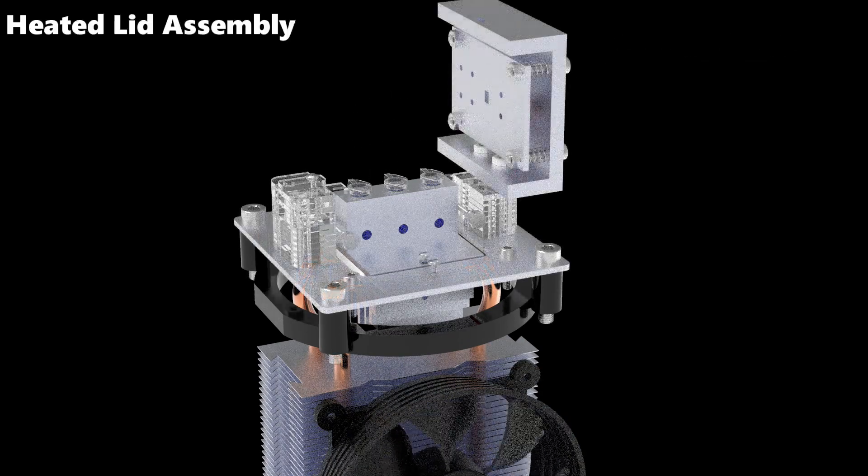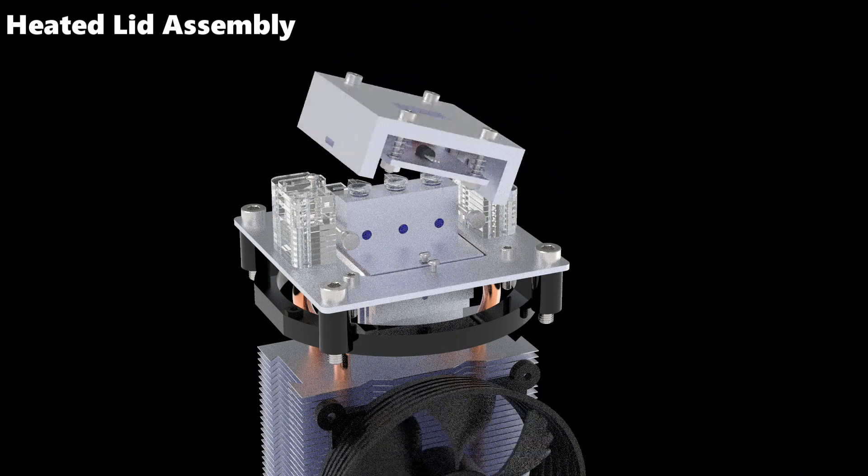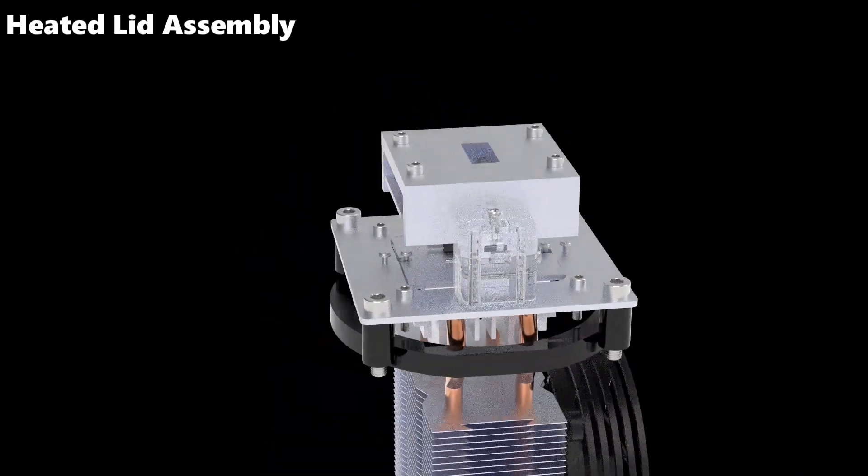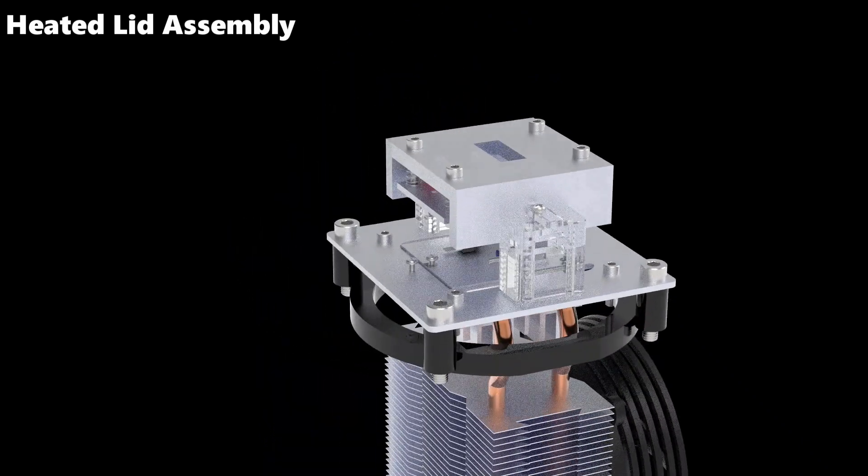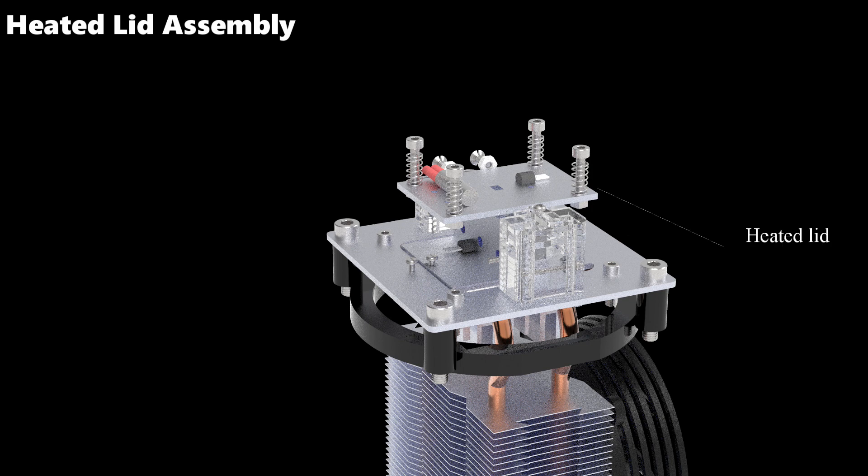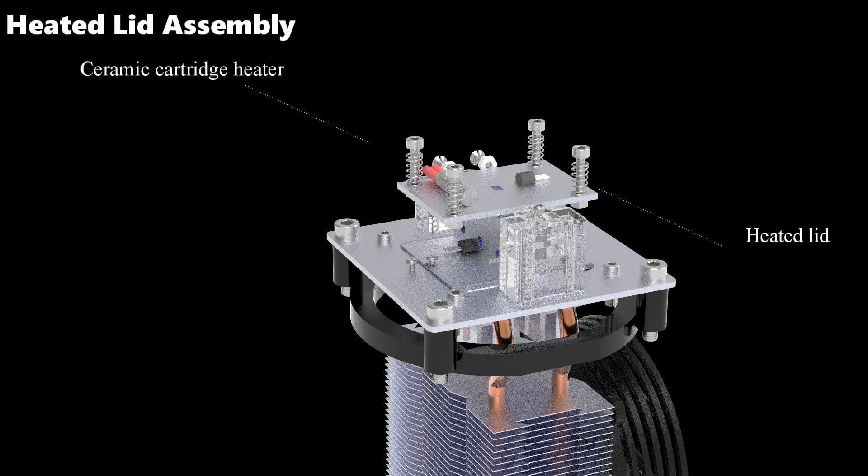To prevent condensation under the tube lid, the tube lid is heated to 100 degrees Celsius. This lid heating is done using a heated lid with a ceramic cartridge heater.